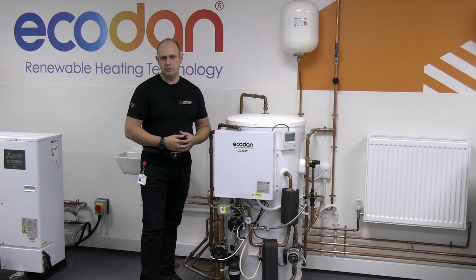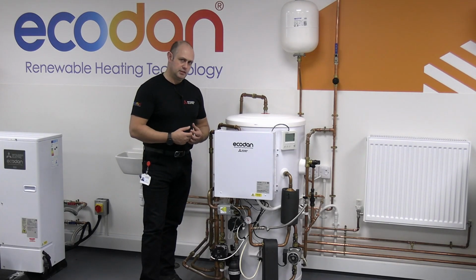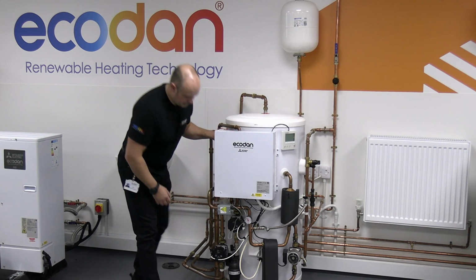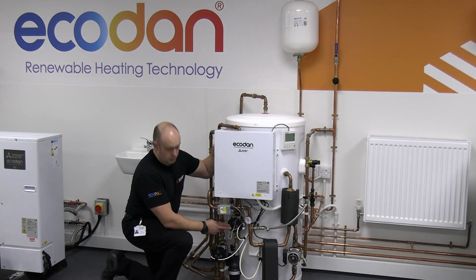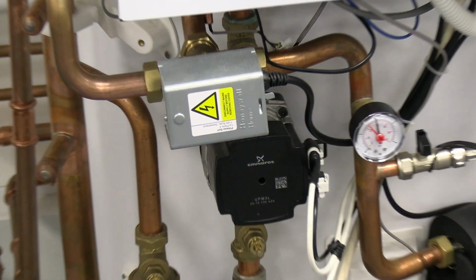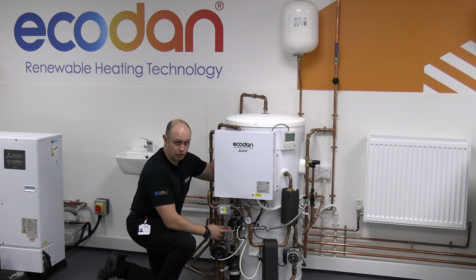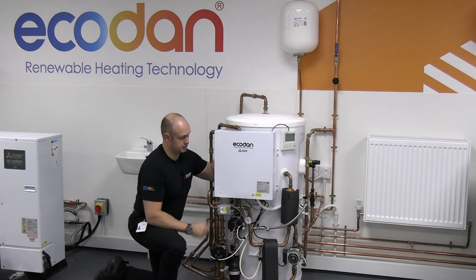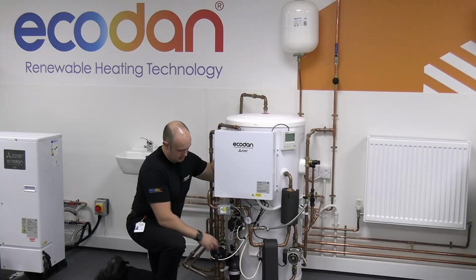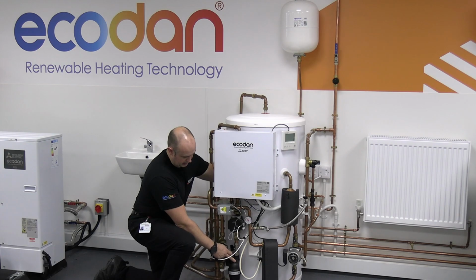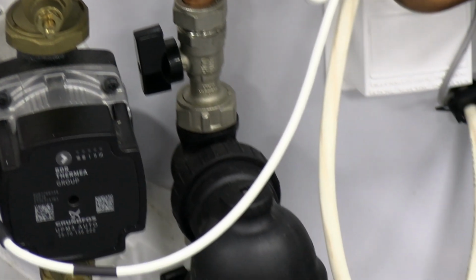Current Mitsubishi pre-plumbed cylinder. First off, we've got a primary pump going to and from the actual cylinder off to the Ecodan. To go along with that, we've got a flow sensor which is sitting behind this cover, and we've also got an inline magnetic and cyclonic filter.